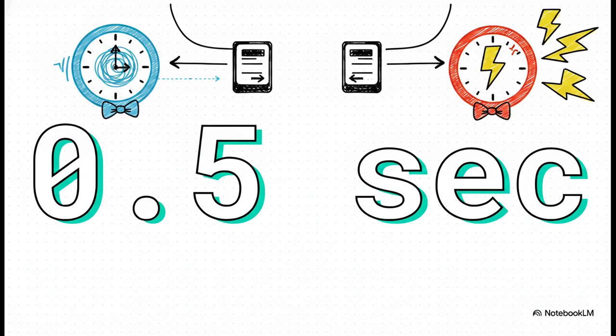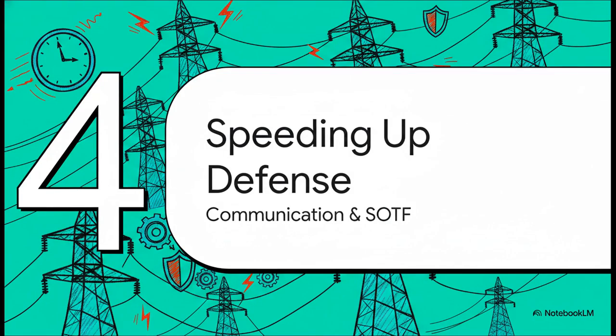Zone 2 waits for this specific amount of time to give the primary relay at the far end a chance to see the fault and clear it first. It's basically a polite, highly disciplined system of, hey, you go first, but if you don't handle it, I absolutely will. Section 4. Speeding up the defense.